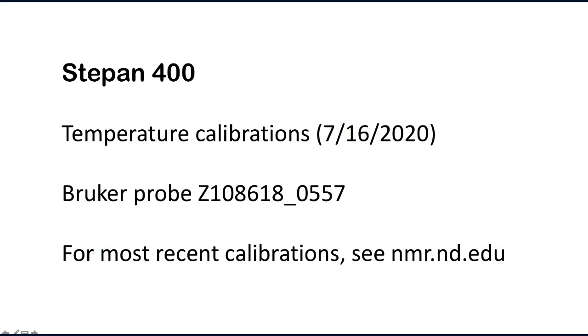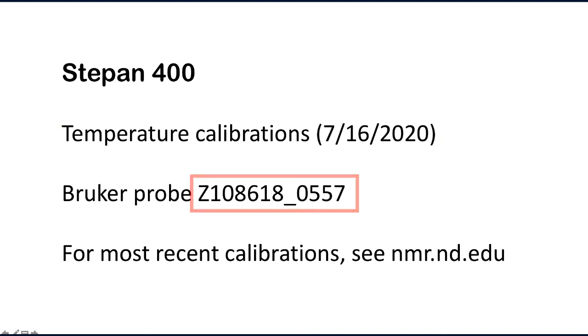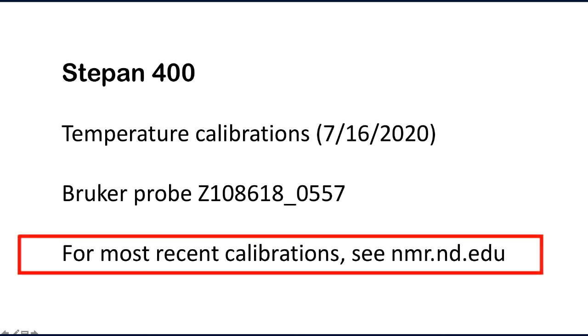At the time of recording of this tutorial, the current calibration is of July 2020. They are strictly specific to the probe. If the probe is changed or goes to repair, it has to be recalibrated. Please make sure that you are using actual most recent calibrations for the specific probe.